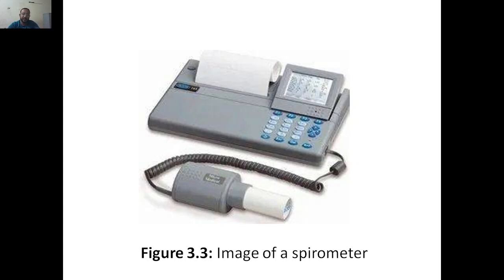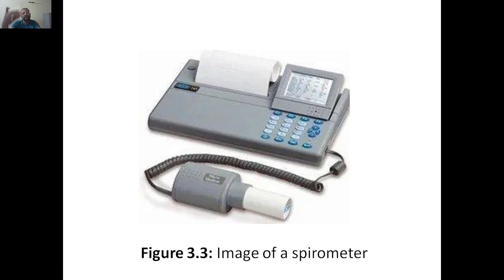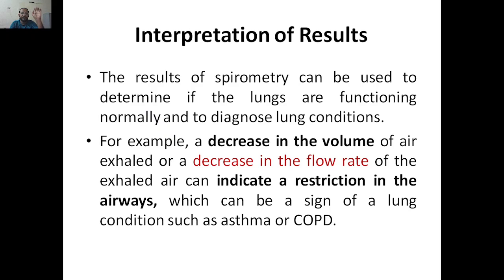This is the image of the spirometer. Here you can see the mouthpiece where the patient will be asked to keep it. This mouthpiece is connected via wire. Along with the mouthpiece we have the sensors — the volume or quantity sensor and the speed or flow sensor. The display shows the results and you can even print the graph. For example, for asthma there will be a different flow-volume pattern, and with the help of that pattern it can tell you whether the person has asthma, COPD, or any other lung-related disorder.